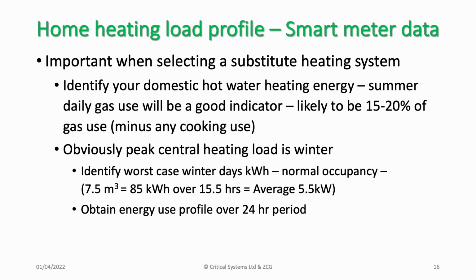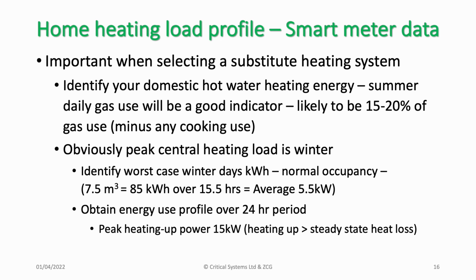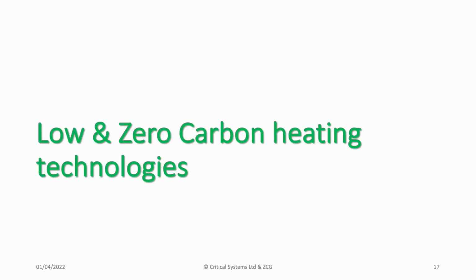We then need to think about the energy profile over a 24-hour period. And evaluating the data in more specific detail, I can establish that the peak heat up power consumption, so this is heating up your house from cold, maybe at 6 o'clock in the morning, in this particular case was 15 kilowatts. And once the air temperature in the controlled spaces had risen to the target set point, a steady state temperature maintenance rate was 9 kilowatts. So I'm starting to understand a lot more about the energy required for the house from the data of the performance of the existing heating system. So with that baseline, I can start to consider some options for low and zero carbon heating technologies.